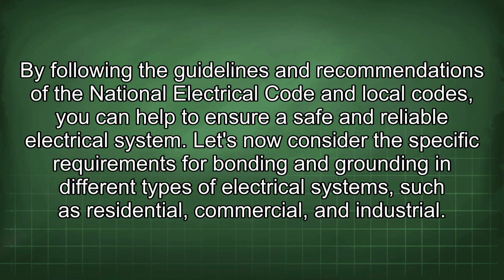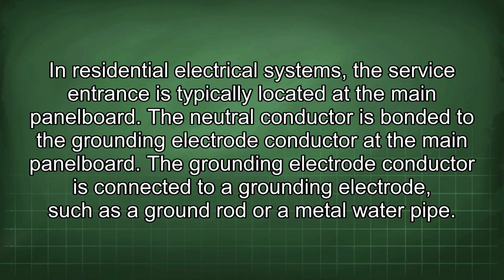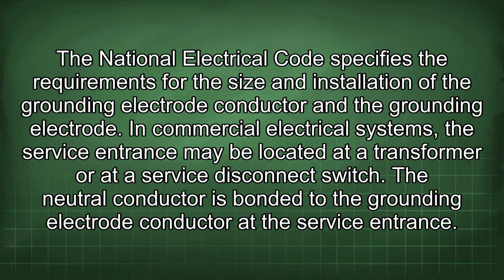Let's now consider the specific requirements for bonding and grounding in different types of electrical systems, such as residential, commercial, and industrial. In residential electrical systems, the service entrance is typically located at the main panel board. The neutral conductor is bonded to the grounding electrode conductor at the main panel board. The grounding electrode conductor is connected to a grounding electrode, such as a ground rod or a metal water pipe. The National Electrical Code specifies the requirements for the size and installation of the grounding electrode conductor and the grounding electrode.